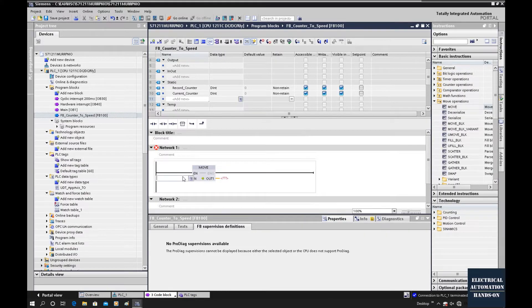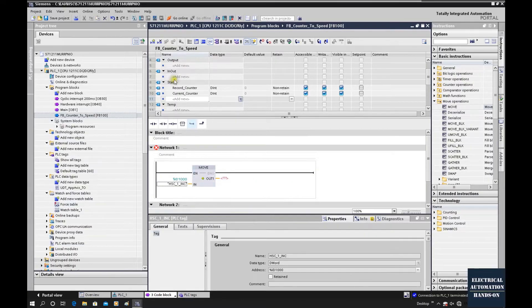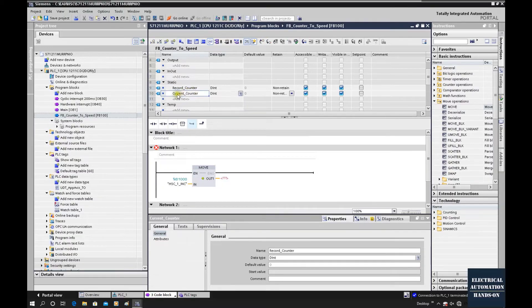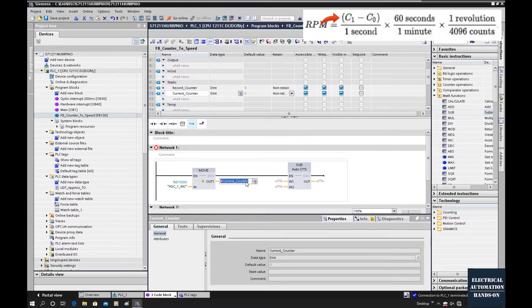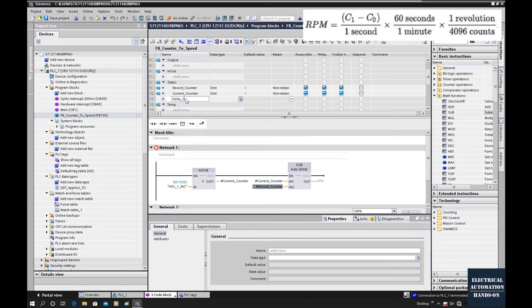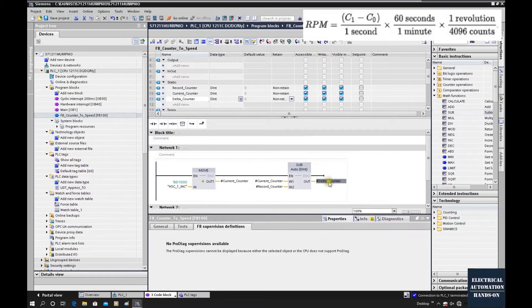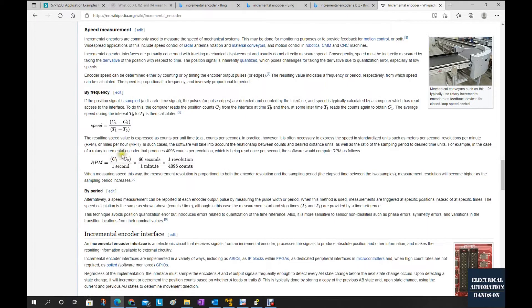In Network 1, we use a MOVE instruction to move the counter value — for example the counter at ID1000 — into Current_Counter. Then we use a math SUB instruction: Current_Counter minus Record_Counter, and the result is the 'Delta_Counter'. All subsequent calculations will use this Delta_Counter, which represents the counter difference over one cyclic interval.